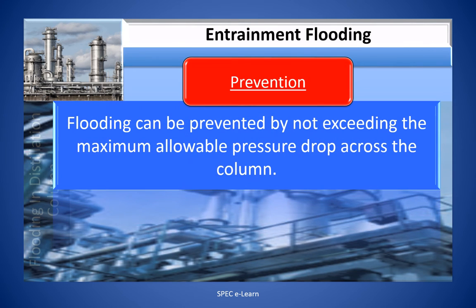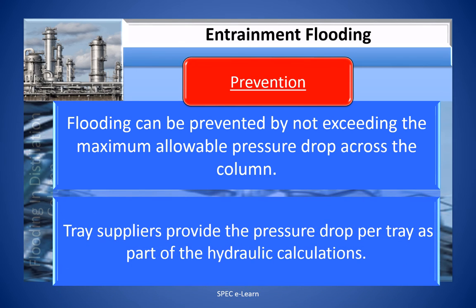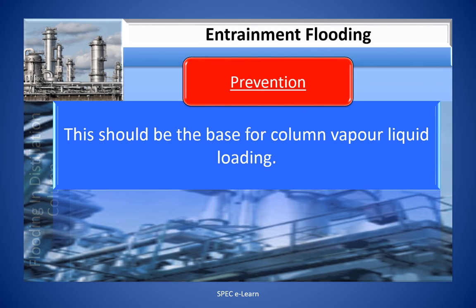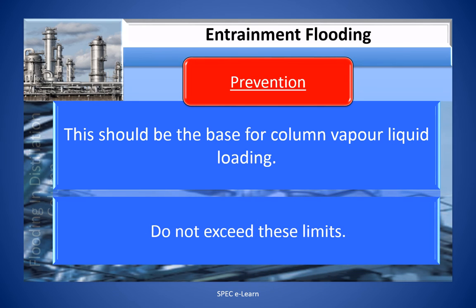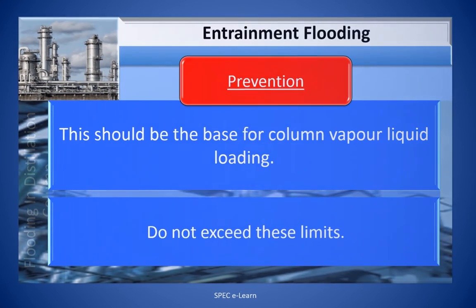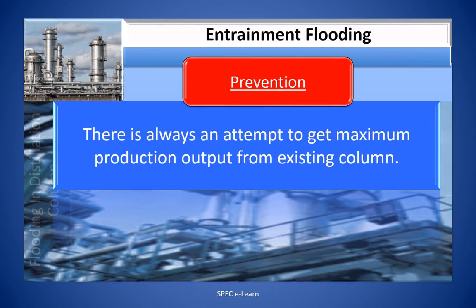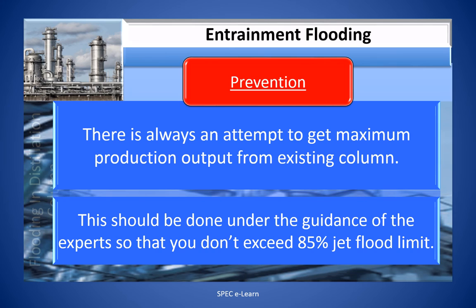Flooding prevention: flooding can be prevented by not exceeding the maximum allowable pressure drop across the column. Tray suppliers provide the pressure drop per tray as part of their hydraulic calculations — this should be the basis for column vapor-liquid loading, and these limits should not be exceeded. There is always an attempt to get maximum production output from an existing column; this should be done under the guidance of experts so that you do not exceed 85% of the jet flood limit.